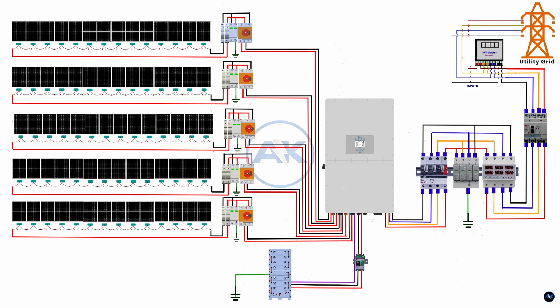Next, install the surge protection device on the AC side. Use a Type 2 AC surge protection device rated for three-phase 4-wire systems. The SPD protects the inverter from lightning and switching surges. Connect each phase and neutral from the line to the SPD terminals, and connect the SPD earth terminal directly to the grounding bar using a short, thick grounding conductor. Proper grounding is essential for the SPD to work correctly.